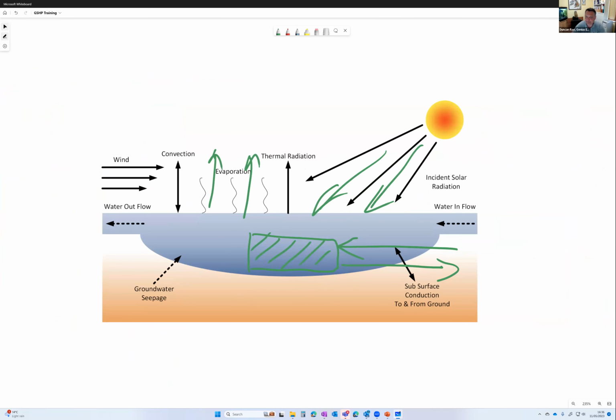Does the pipework ever leak? I've been responsible for something like 50,000 boreholes in the 20 years I've been involved in ground source. During installation you get pipe failures and they're remediated at installation, so you're testing as you install. That absolutely does happen. But post-installation, in those 50,000 boreholes, I know of only 3 that have failed, and they're actually all in one project. We believe the coal mine that we were drilling through has either collapsed or gone on fire, and it's destroyed 3 boreholes. So it's very unusual for installations to fail post-installation.